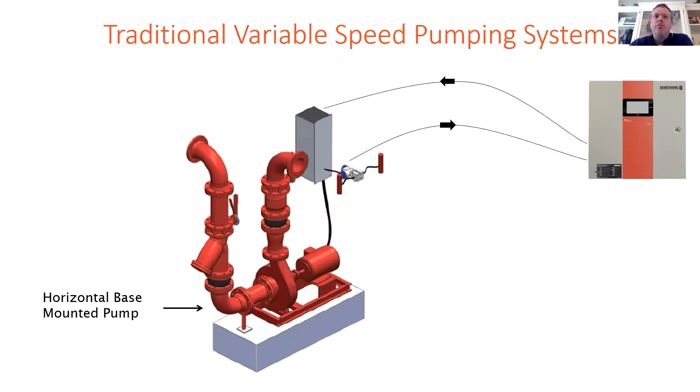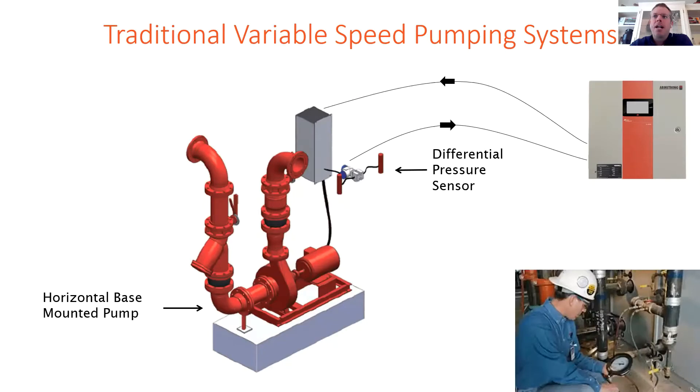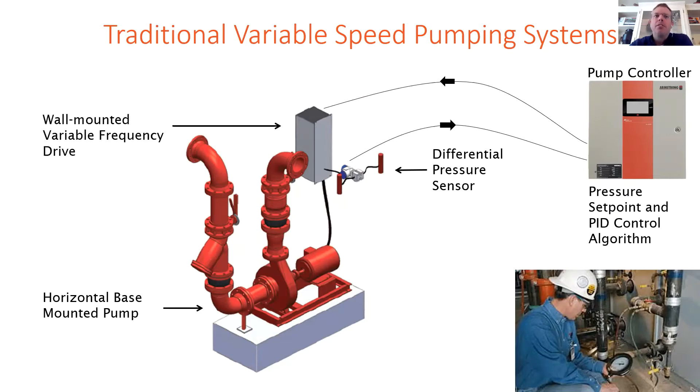So with a traditional variable speed pumping system, there's a differential pressure sensor that's located out in the system somewhere. Via a test and balance contractor, a minimum pressure set point is determined, which will satisfy the most remote load during normal operation. The pump controller is then going to vary the speed of the pump motor via variable frequency drive to ensure that the differential pressure set point is maintained as two-way valves open and close out of the system.